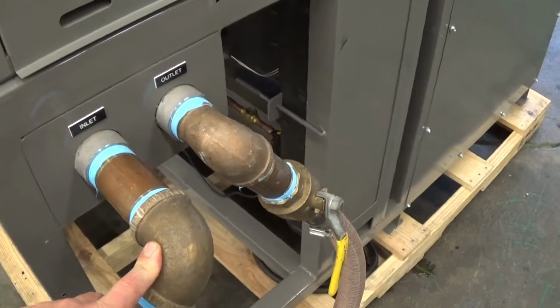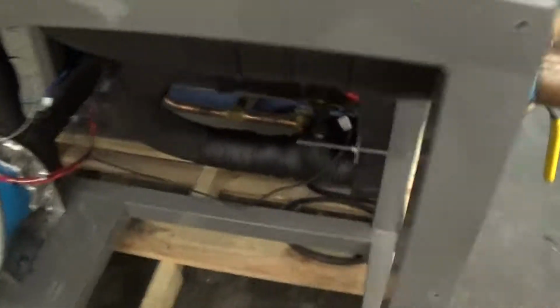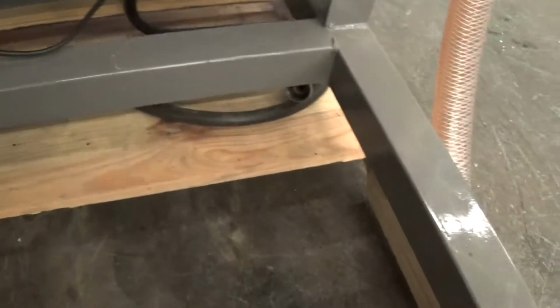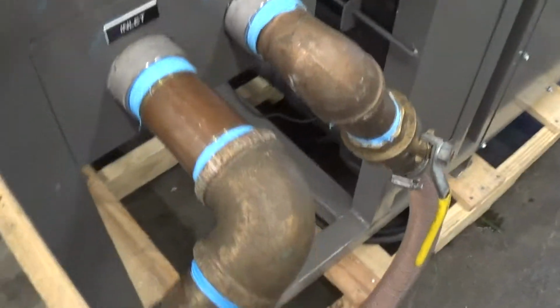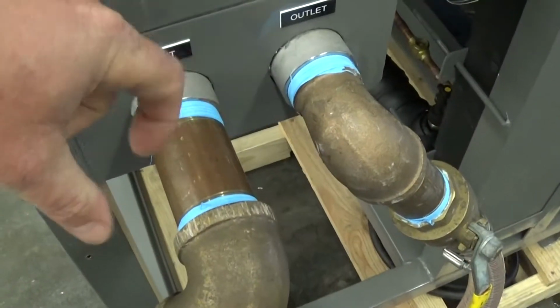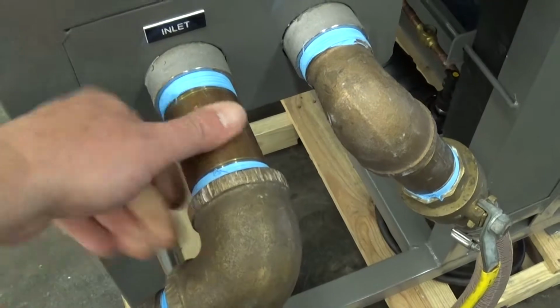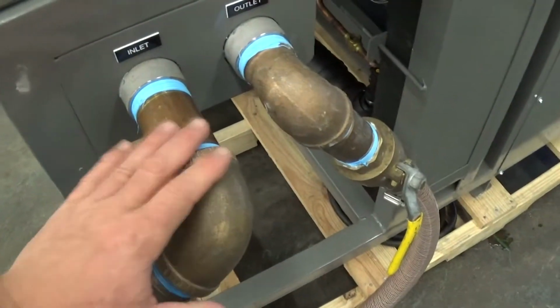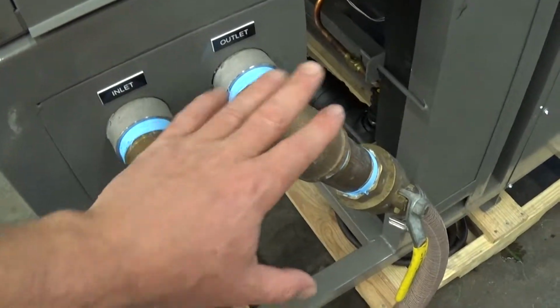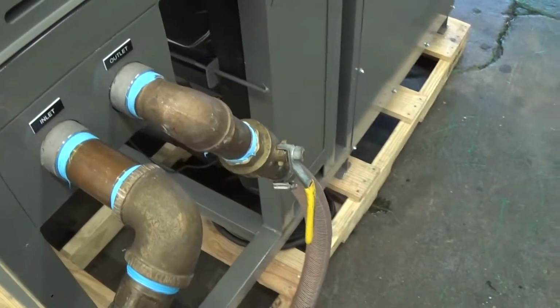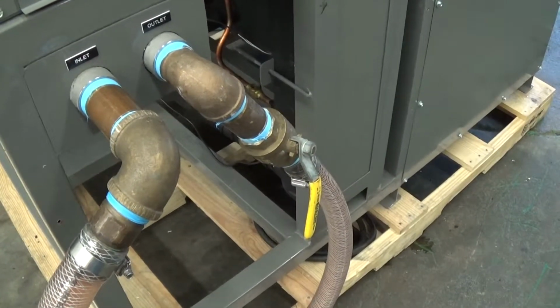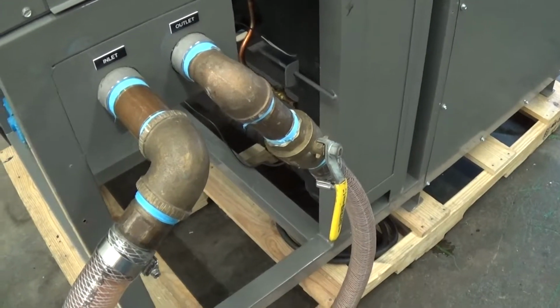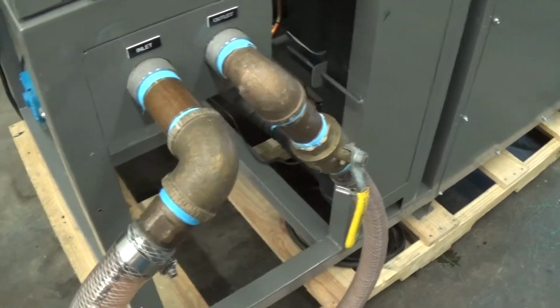Now, for filling the tank when you get it, you can do one of 2 things. We do have a drain that has a shut-off there. You can either hook up a hose, you're probably going to be running Glycol, a hose and a pump, and you can pump it in that way. Or it's good practice, per the manual, to put a T here with the top of the T facing upwards for the initial filling, and you put a cap on that. Ideally, you want to have some shutoffs both at your inlet and outlet. And then for this application where your supply meets the return, you should put either a shutoff or, even better, a pressure relief bypass valve. And we'll email the customer, or can email anybody who's interested in learning more about what part to get.